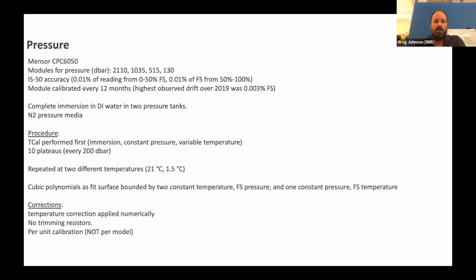If you're used to a deadweight tester, the percentage accuracy on a deadweight tester is normally a percent of reading. But we're trying to calibrate a pressure gauge, which is spec'd in terms of percent of full scale. Well, these quartz-based gauges have a specification that is a hybrid of the two. So the IS50 means that for whatever gauge we're using, let's say we're using the 130 dbar gauge, the accuracy of it is 0.01% of reading for the first 50% of the scale, so up to 65 dbar. So that's a line that increases as the reading increases. And then after that, it changes to 0.01% of full scale from 50 to 100%, and so the line goes horizontal. I want to make sure I haven't done it the wrong way around. No, I've done it the right way around. Sorry, I'm trying to draw backwards in my head.